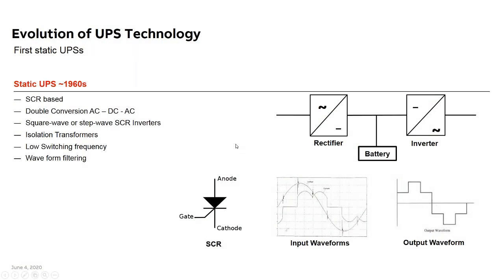So looking into how did this all start and what has happened? Static UPSs have actually been around since the 60s. It actually started when somebody invented the silicon controlled rectifier, an SCR, and smart engineers figured out that there were a number of different ways they could utilize that component. One of them was as a UPS. So the first UPSs are actually from the 60s and based on SCRs.